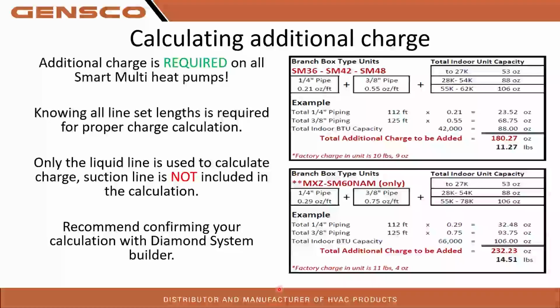The other nice thing with using Diamond System Builder, or even with this, is when you're doing your sales bids, if you build the system in Diamond System Builder, which you should be, it's going to tell you your estimated BTU output for the system. It's going to tell you if you have a compatible system, you're following all the rules of the system, the additional charge, and it gives you a good ballpark for your estimates as well. You may not know exact pipe lengths, but you can get pretty darn close to what you're expecting on your bid and be able to figure out how much charge you're going to need and add that to your bid as well.